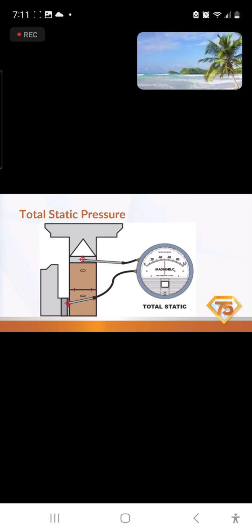You could remove the filter and put your pressure sensor right there in the door for the filter and seal up around it and check your return static there. Alternatively, if you needed to, you could drill a small hole on the side of the furnace, opposite side of the filter in this application, and check it right there as well. But when we're checking our total static, we do not want to include the filter. We do not want to include the coil. So I know that can be difficult at times, but there are ways around it.